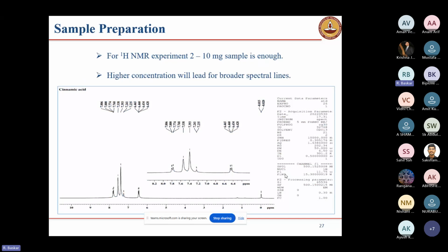Next, sample preparation. You can synthesize very excellent compounds, but if you do not prepare a good sample, you will get a bad NMR spectrum. Sample preparation is the most important. For proton NMR, you have to take the minimum sample. 2 to 10 mg is more than enough. If you take the maximum, it will affect the shimming. You'll get broader signals and won't get sharper signals. So sample preparation is the most important. For proton NMR, we need to take 2 to 10 milligrams.